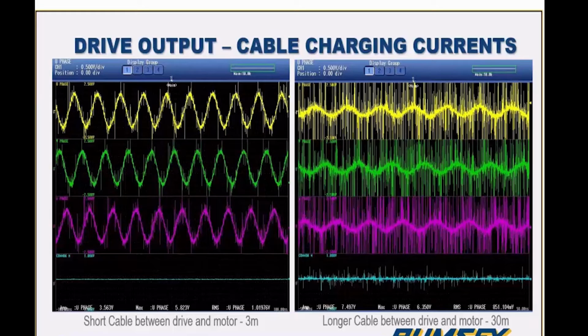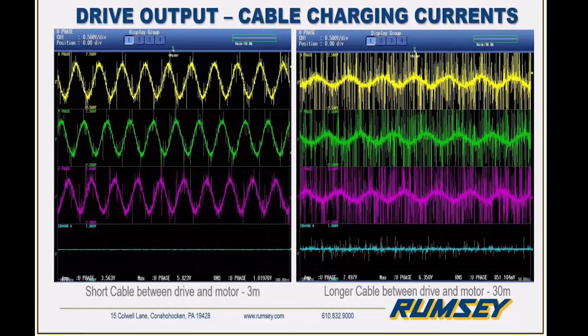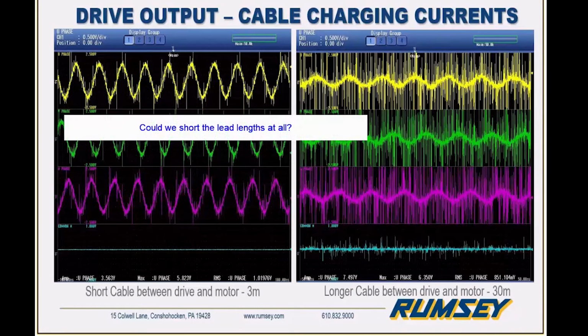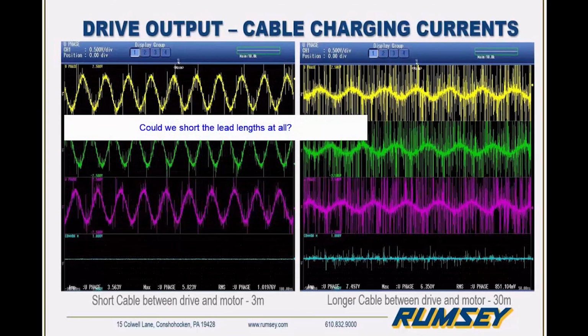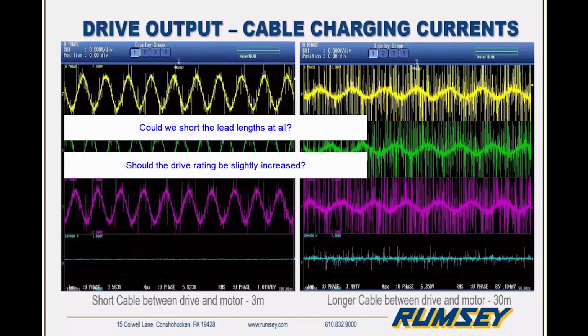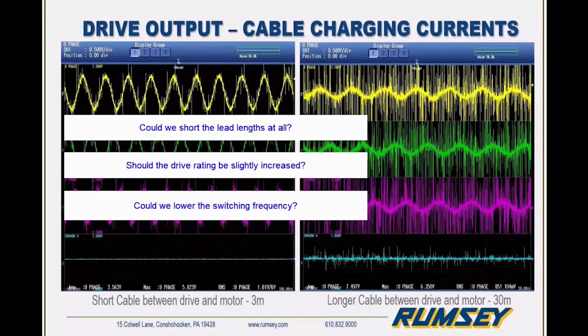So in order to eliminate that up front, if we know we have an installation and the lead lengths might be getting kind of far, the first thing to consider would be how can we shorten those lead lengths if at all possible. Another thing we could do would be to slightly increase the rating or size of that drive from the start. Also, we can lower the switching frequency.